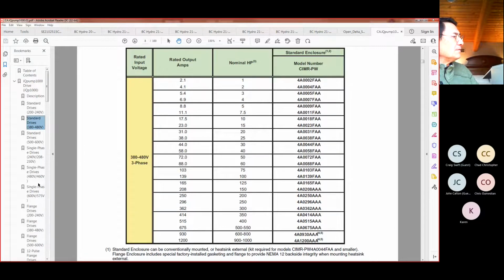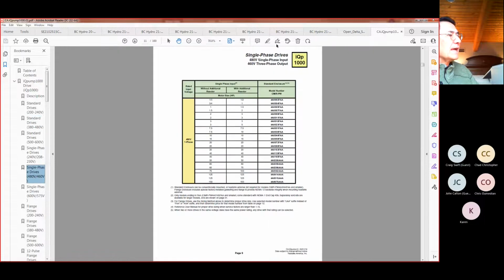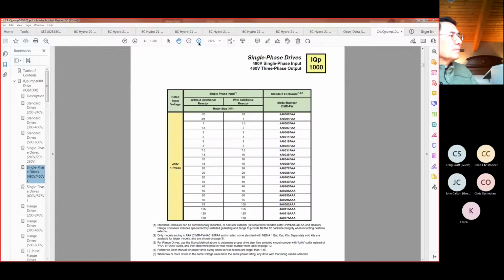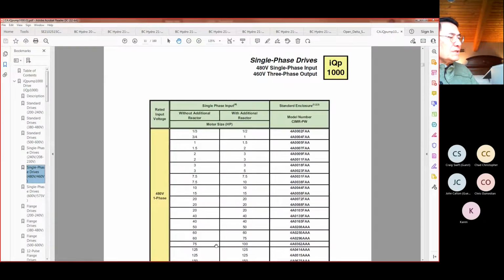If we go to the single phase version of that and we go to 75 horsepower, we will see that we are in a 362 amp drive without additional reactor. And if we add an additional reactor, the 75 horsepower application will require a 296 amp drive.